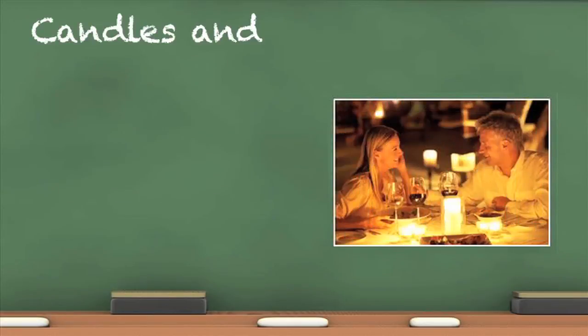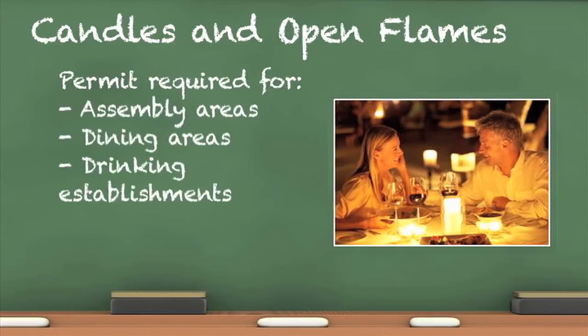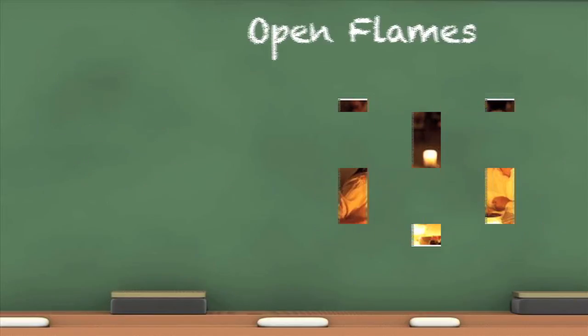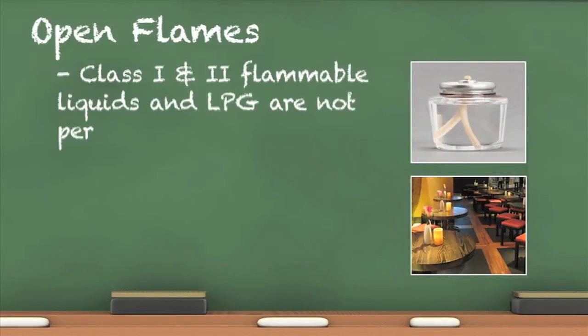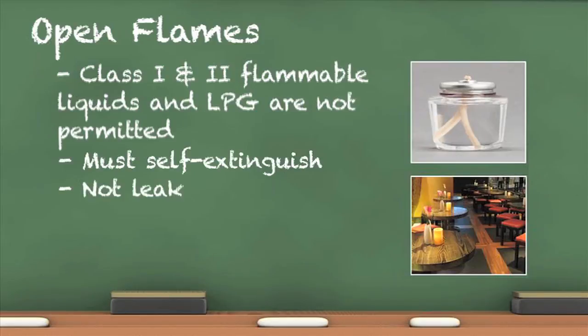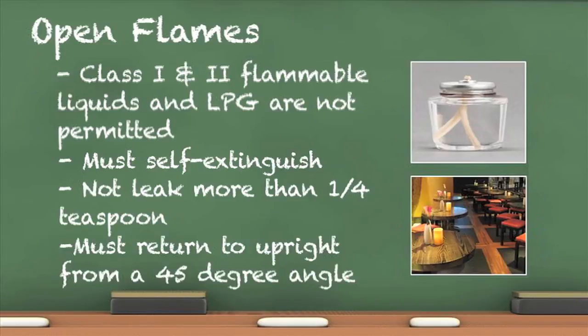A permit is required to use an open flame or candle in connection with assembly areas, the dining area of restaurants, or drinking establishments. Once the inspection has been finalized and all violations, if any, are corrected, the fire inspection report is your permit from the fire department to have candles and open flames. Stringent regulations govern open flames in the A occupancy: Class 1 and 2 flammables are not permitted. Lighting devices with more than 8 ounces of fuel are required to be self-extinguishing and not leak more than a quarter teaspoon per minute when tipped over. If the lighting device does not self-extinguish when tipped over, it must self-return to an upright position.